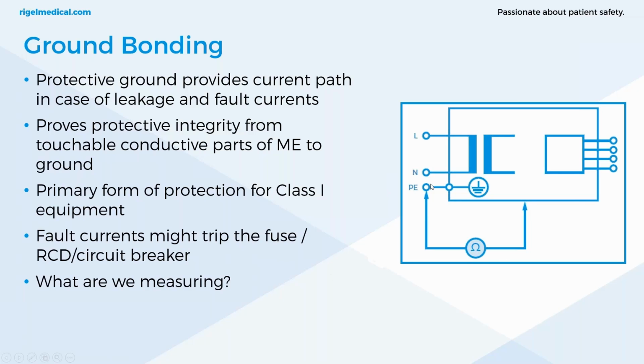What are we measuring? We're using an ohmmeter to measure resistance between exposed conductors and protective earth. The lower the values, the better, but limits will be stated in the specific standard. Measuring currents are not always mentioned. In the NFPA 99, the current values are not necessarily mentioned. They just give you examples of how you can measure the resistance between these two points. But the majority of users will be utilizing an electrical safety analyzer, which will have a method that's approved by that standard. So I've just got some questions.